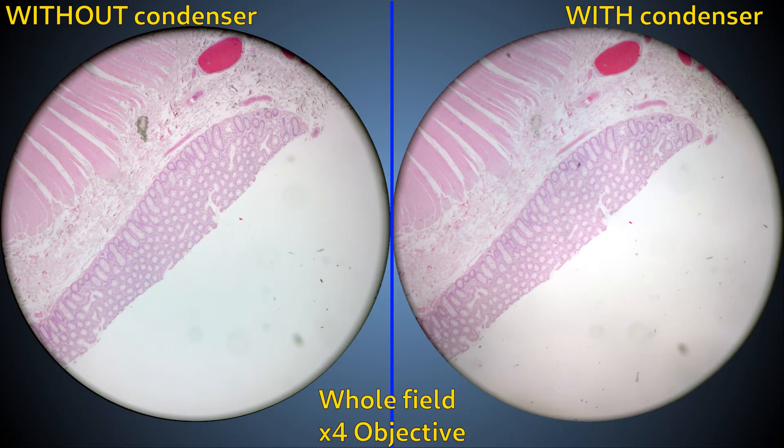With low magnification objectives, such as 4x, there does not at first seem to be much advantage of having a condenser. In fact, there is even a disadvantage in that the condenser image has uneven illumination, being darker at the periphery compared to the condenser-less microscope. There are some things you can do to fix this, but I'll discuss those in another tutorial.